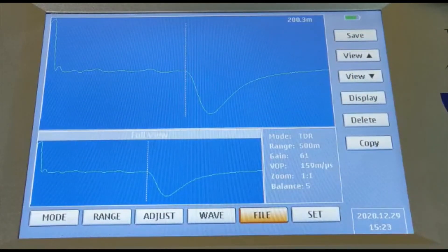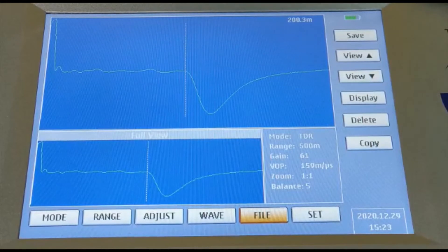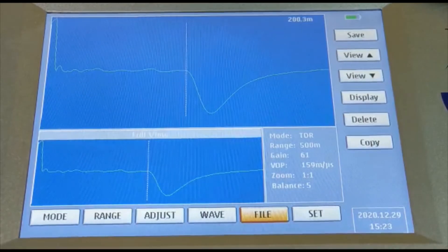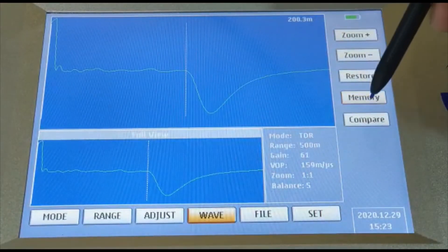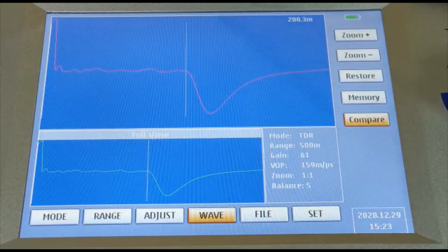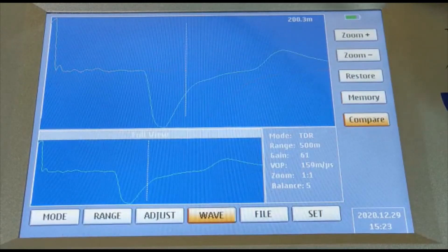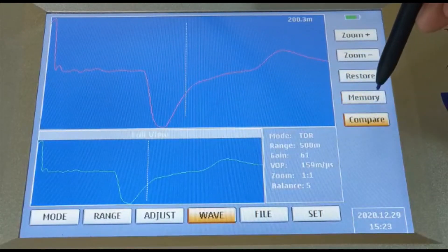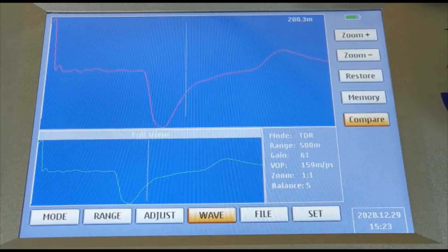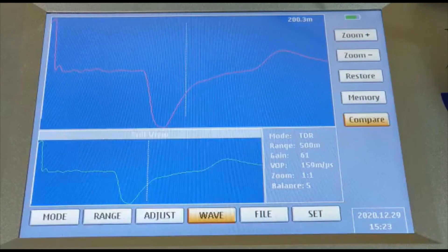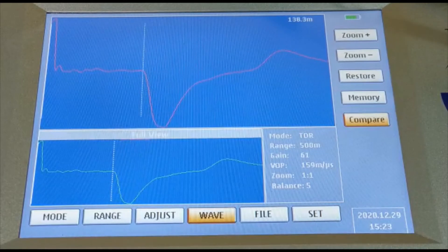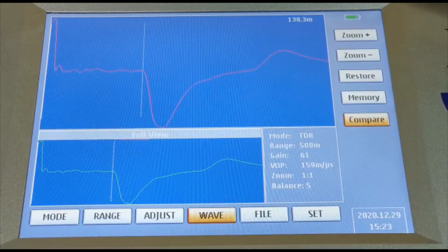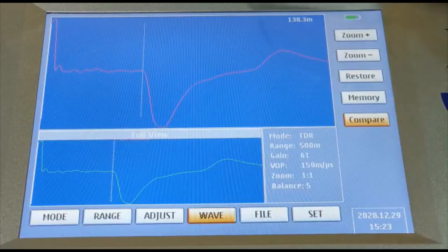If you want to see different distances, we can create a short circuit fault in between the cable and see what happens. Go to wave, go to memorize, then compare, then press test. You can see that the distance has changed to a different fault location — the fault distance is now 138 meters. Now I create an open circuit fault at 138 meters.